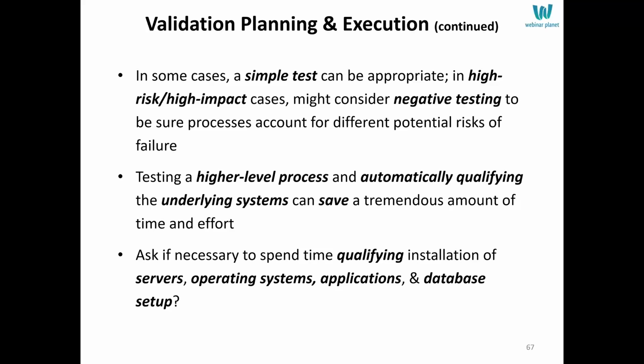And when you test a higher level process, you may automatically qualify the underlying systems and save a lot of time and effort. So for example, you would never do an OQ on a server, operating system, application database setup. You don't do anything but an IQ on those things.